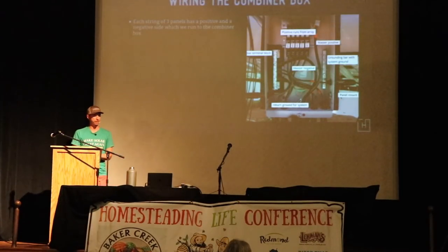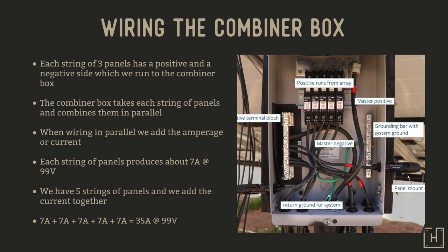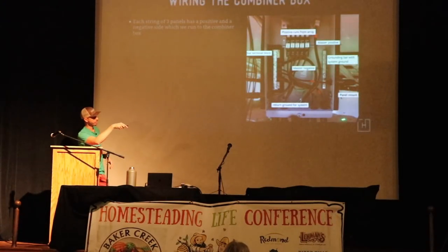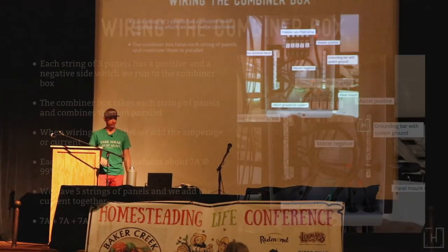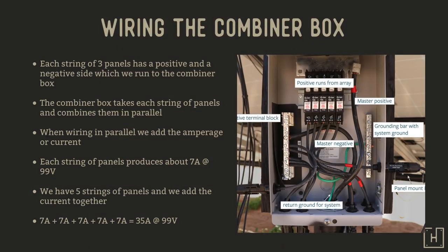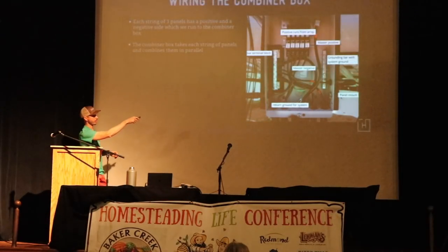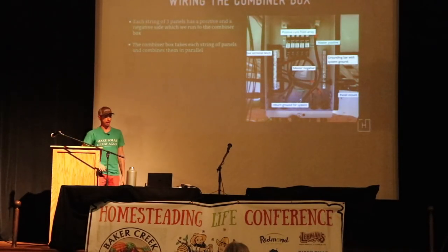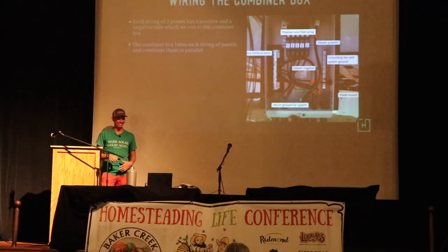When we come into the combiner, each string of three panels has both a positive side and a negative side, and we run that to what is called the combiner box. This is my combiner box here. The strings coming from the panels run either into the side or come up through the bottom. The combiner box takes each of those strings of panels and combines them in parallel. These connections right on the side here are parallel connections. I don't want to go into too much detail about the difference, might get a little too nerdy.